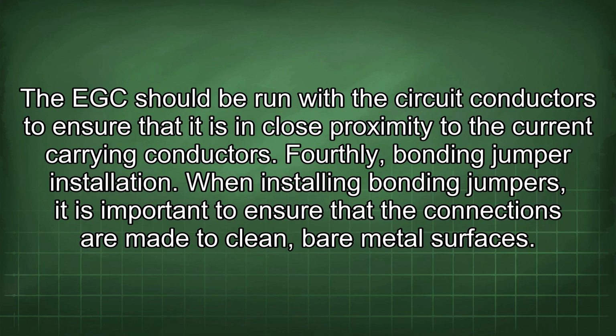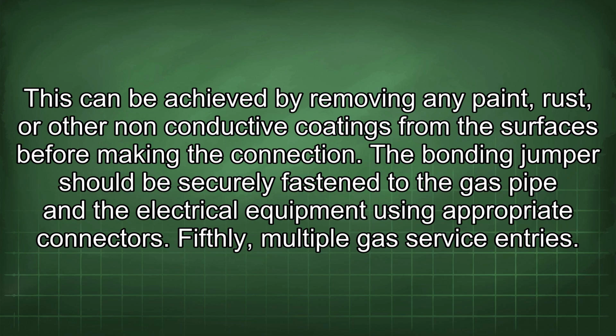Fourthly, bonding jumper installation. When installing bonding jumpers, it is important to ensure that the connections are made to clean, bare metal surfaces. This can be achieved by removing any paint, rust, or other non-conductive coatings from the surfaces before making the connection. The bonding jumper should be securely fastened to the gas pipe and the electrical equipment using appropriate connectors.